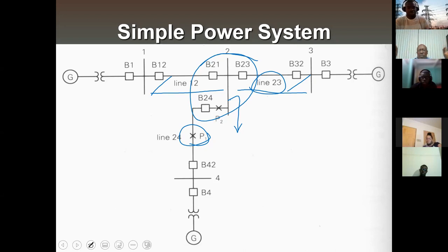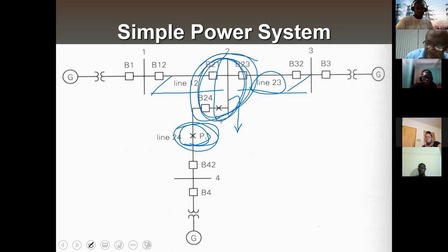You would trip 1-2 and 3-2 based on that escalation, if within your system the mechanism is such that once one breaker on the line opens, the other opens. Yes? But in this instance, the fault is really down here. Yes? The fault is really down there. And what you have is an escalation, so it's taking out the bus bar breakers.